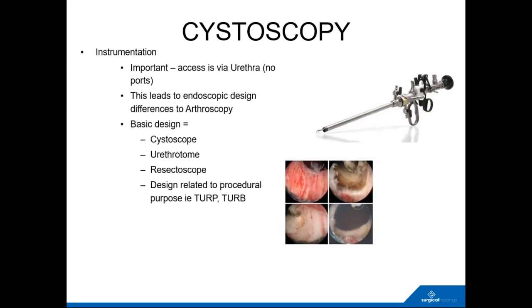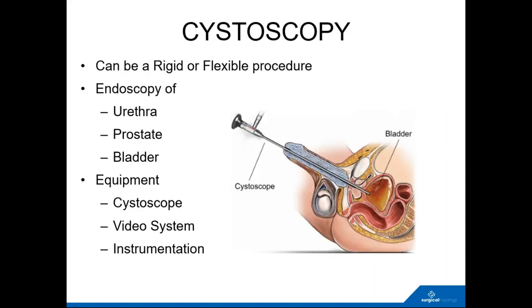Sorry, Nick, just one question that came up from my perspective. You described the different angles of the scopes, and this is why it's so important that when scopes are maintained through the course of their life, they have the correct lenses and angles and specifications adhered to. Is that right? Yeah, absolutely. One of the things I'll show you in a minute is TUR, a transurethral resection, so a resectoscope. If incorrect lenses are put into that, and you get the wrong field of view and direction of view, and you're trying to do a resection, you may not see what you want to see. Typically you won't see the beak of the sheath, for example. So it is very important that the repairer is using the appropriate lenses and getting the appropriate field of view and direction of view. Okay, sorry for interrupting.